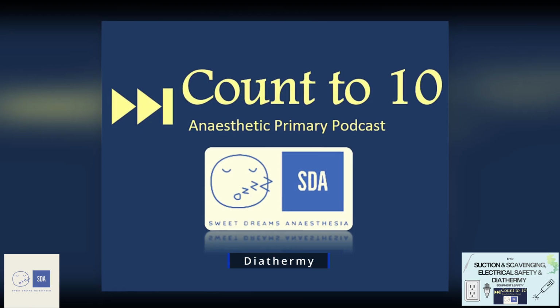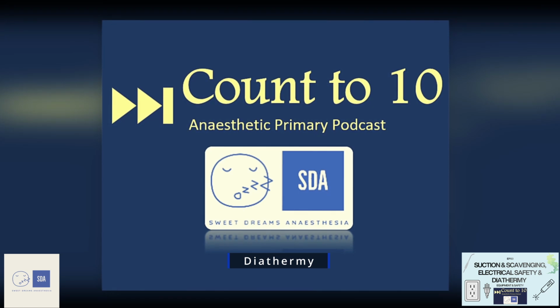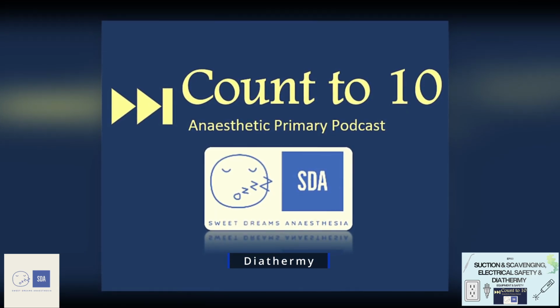The unipolar diathermy consists of a probe containing one electrode and then a large surface area plate that's attached to a patient. You'll see this in theatre as the blue plate that attaches to the patient. This is called the ground plate. The current density at the forceps or the electrode is really high, and this allows heating in the form of cutting or coagulating. But the current density at the ground plate is low, because remember, the equation for current density is current divided by area. And because of a large ground plate, there's little heating at this area. That's why when you take the ground plate off the patient, there isn't really any burns there.